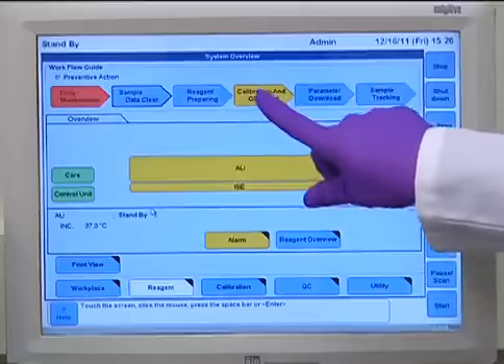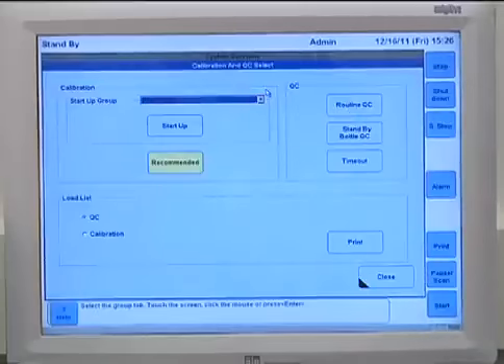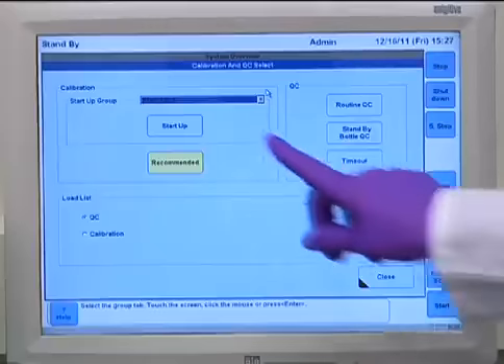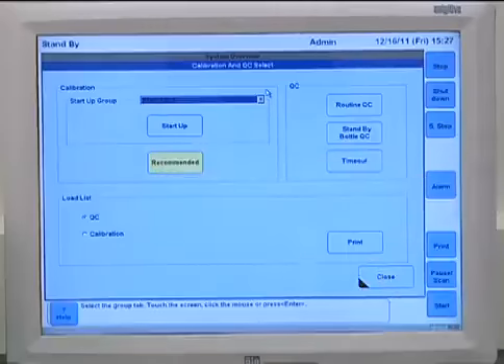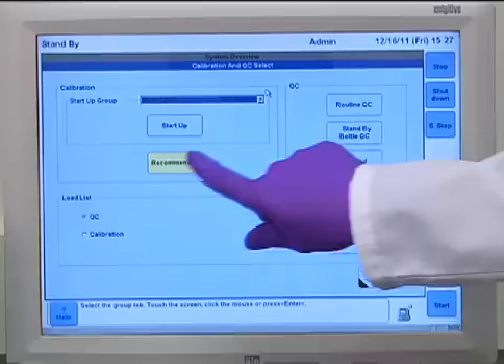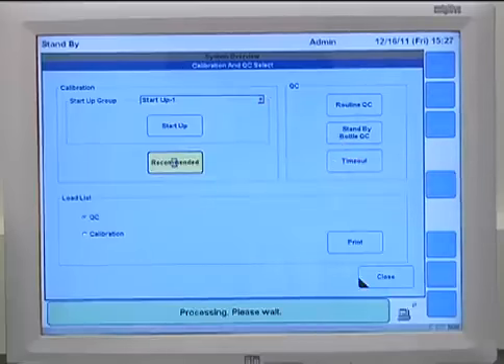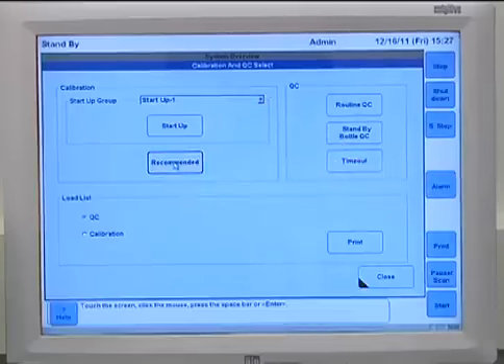And as you can see, my button is yellow, telling me that something is due. Looking at the screen, I have a yellow button that's called recommended, and that's telling me that the instrument is recommending a calibration. And this is linked to our preventive action when we turned it on to let us know that calibrations will be due in the next 24 hours. So by simply selecting recommended, I am ordering all of the due calibrations.